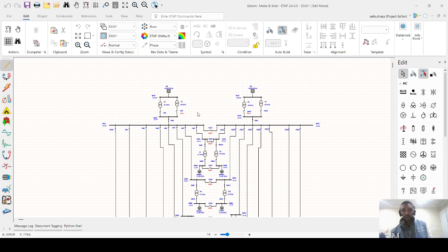So, this is the overview of my structure. Each 22 kV bus is supplied equally from the Matla as well as the Kriel power station. This is achieved by connecting buses radially to a common 22 kV bus, which is this one, that feeds from both the mentioned power stations via this tiebreaker CB13, ensuring a 50-50 split power delivery.